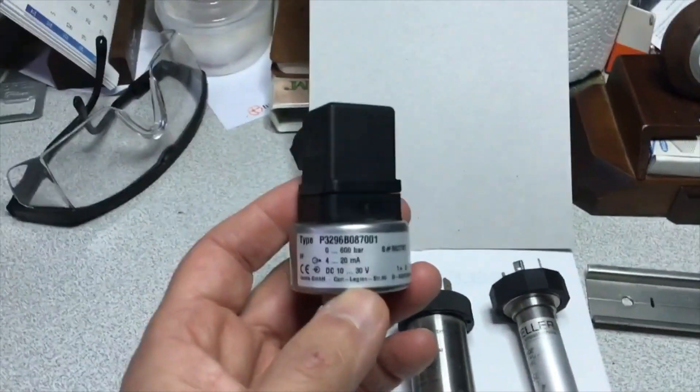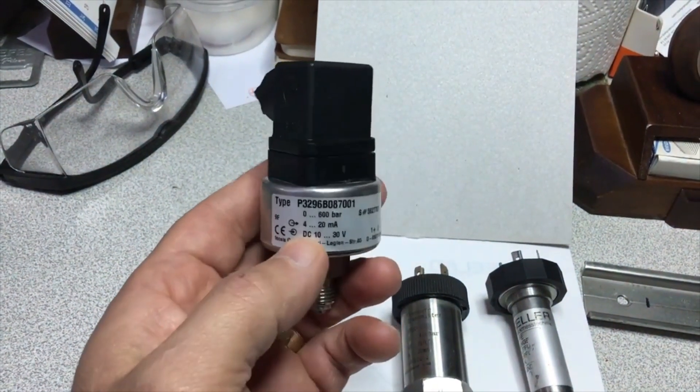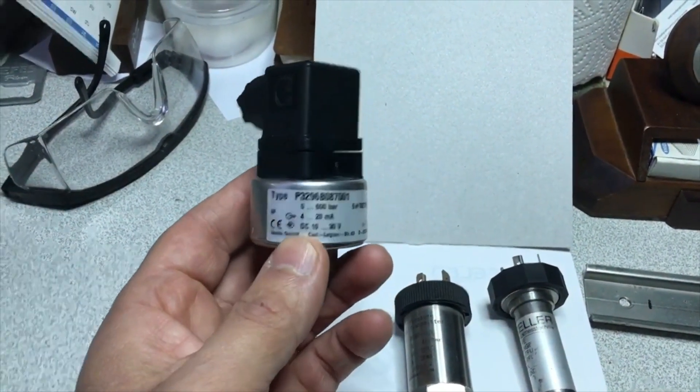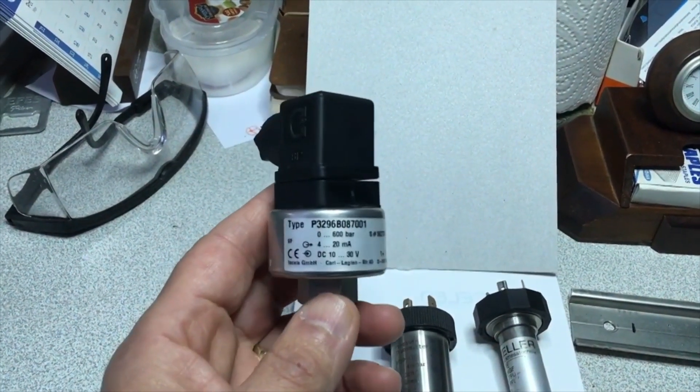Apart from that, it is written that the output current is 4 to 20 milliamperes. The supply voltage is seen to be between 10 to 30 volts. As you know, since we usually use 24 volt DC supply in industrial automation, it meets these limits and stays between the limits.